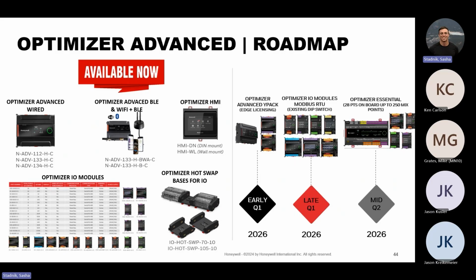Could be with or without display, so we have different models. It will come with a 100 points license on the edge with unlimited SMA. From those 100 points, you can choose from BACnet, Modbus, Panel Bus, but it's a mix of hardware and software points. You can upgrade it to advanced, but you cannot go beyond that 100 points on the edge. The moment you upgrade it, you lose the SMA. That's standard across Tridium, what we call the portability license.